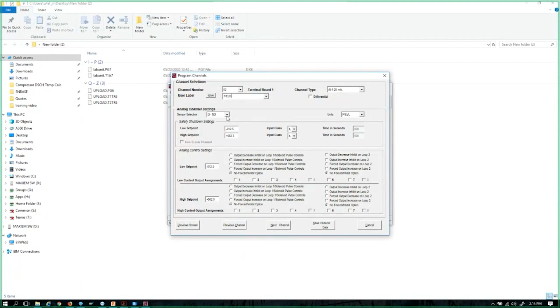The first thing you want to do after you've set up this top part is select what your pressure range is, but be cautious here. When you're doing a 4 to 20, never select pressure from this drop-down list, even though your pressure transducer may be a 0 to 2000. This drop-down list is reserved for the Altronic standard 0 to 5 volt pressure transducers, not 4 to 20s. If you have a 0 to 2000 pound 4 to 20 milliamp pressure transducer and you select this option, the scaling will be off. So what you want to do on a 4 to 20 is always select other.